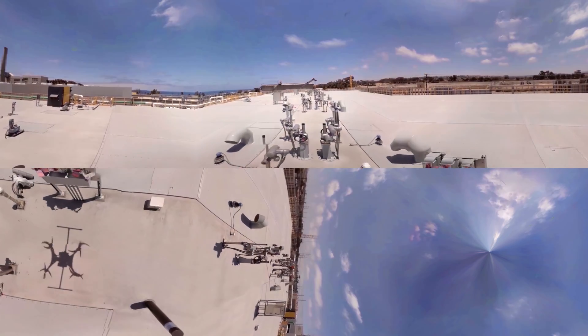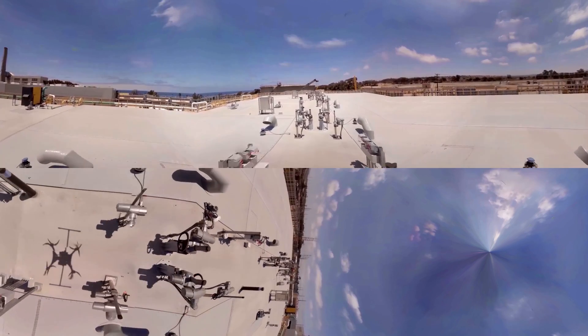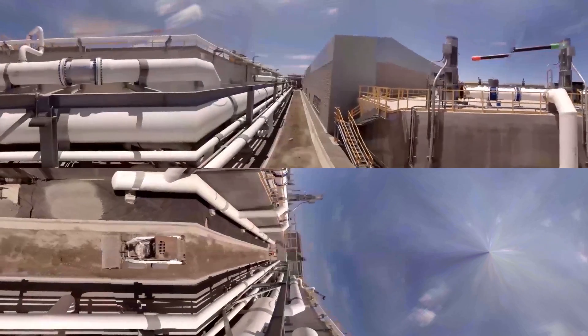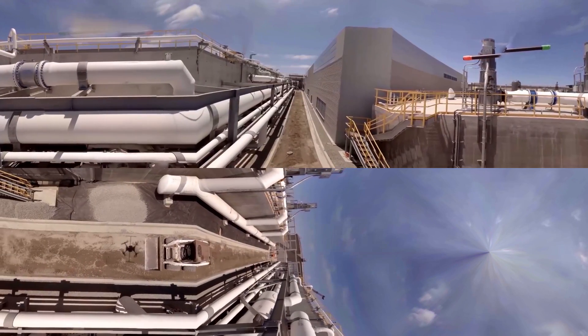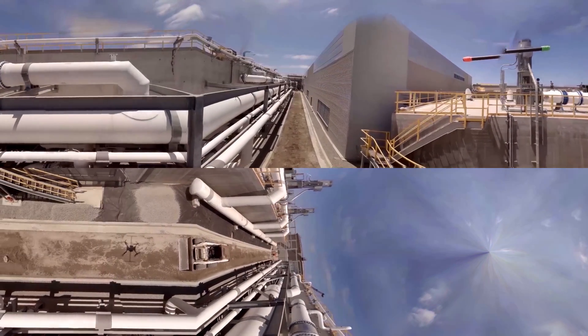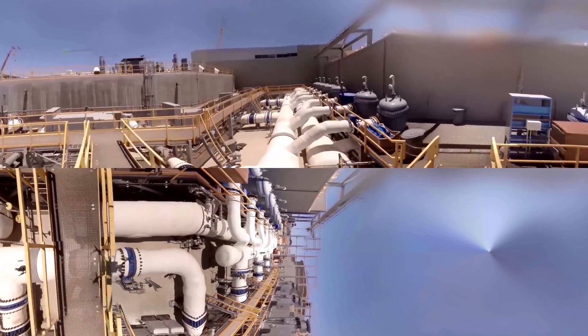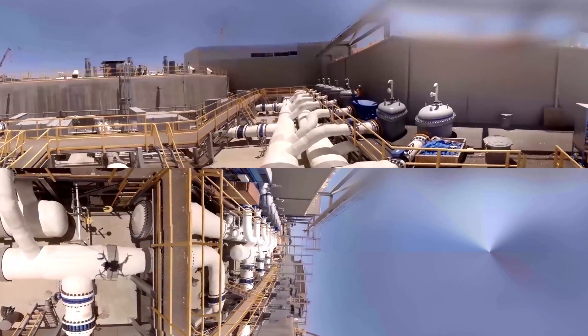Pre-treatment. Seawater desalination begins with several innovative pre-treatment processes. At first, the seawater is flocculated in four chambers and filtered by 18 dual media filters. The water then flows into the 757,000 gallon clear water tank, where it is boosted through a set of 16 micronic filters.